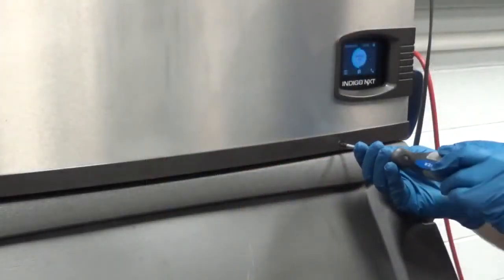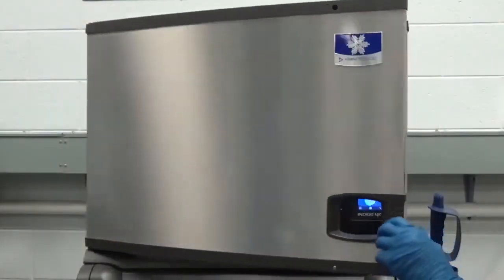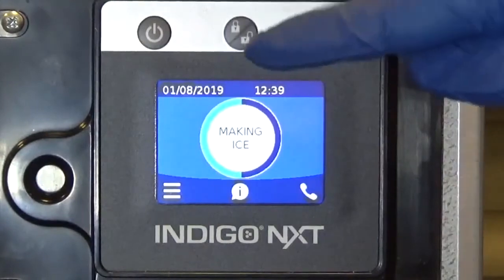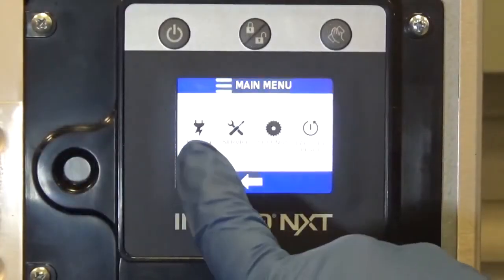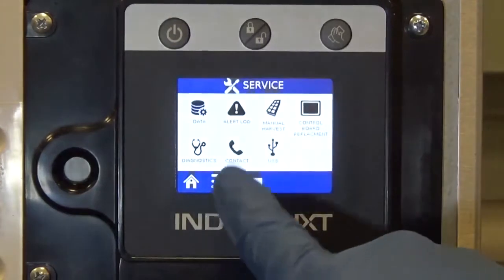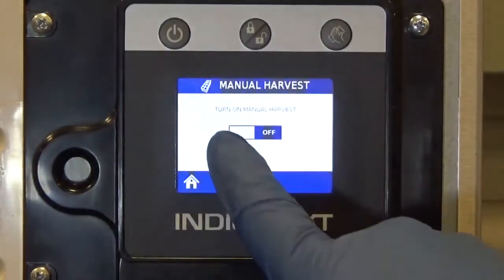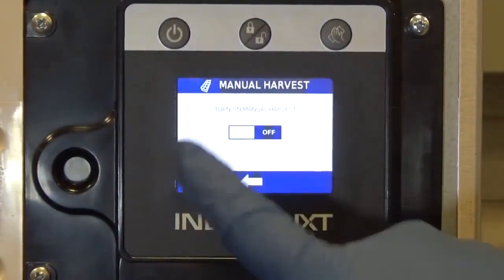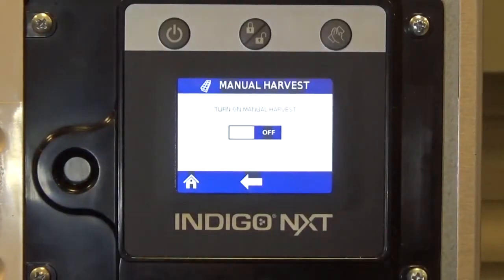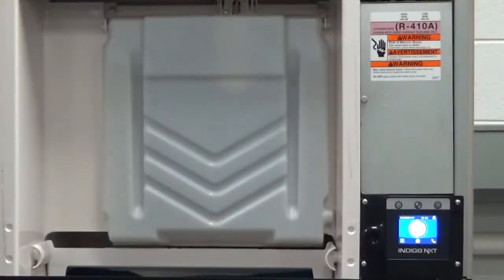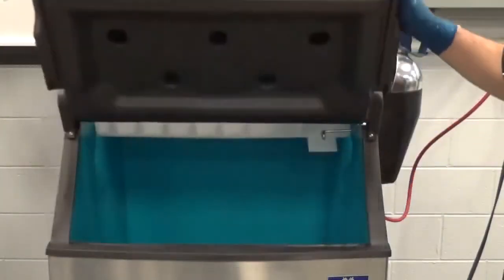Step 1. Open the front cover and then put the machine into manual harvest. Note: although not required and dependent on your installation, removing the ice machine top cover may allow easier access. An alternative to manual harvest is to program the ice machine off, allowing the ice in the bin to be used up or melt. Never use anything to force ice from the evaporator. Damage may result. Step 2. Remove all the ice from the bin.